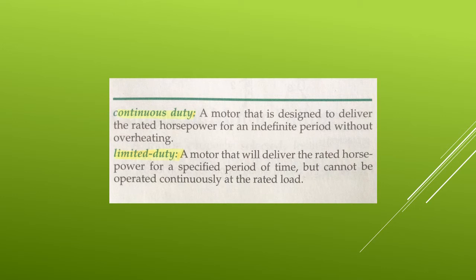Limited duty motors will deliver rated horsepower for a specified period of time but cannot be operated continuously at the rated load. A limited duty motor is one used to operate valves, pumps, or elevators. If its operating period is extended, a limited duty motor will overheat and may burn out prematurely.